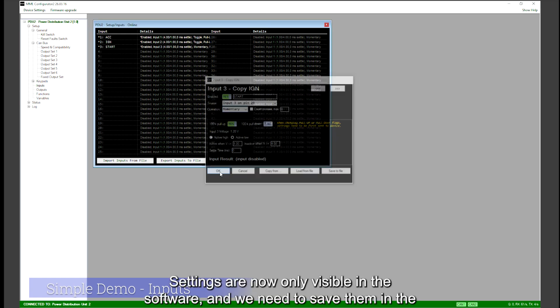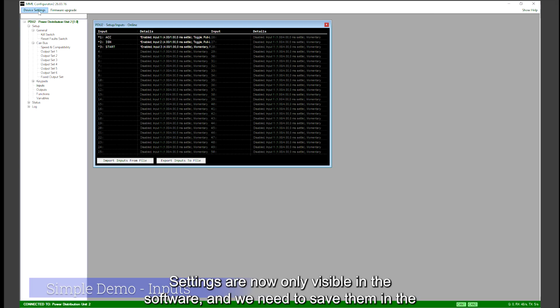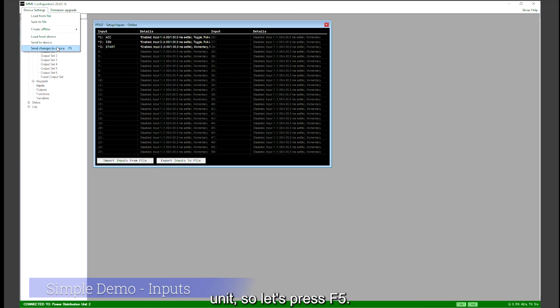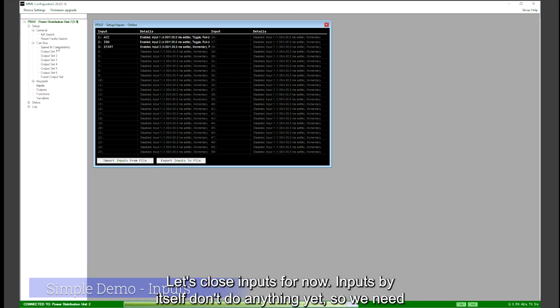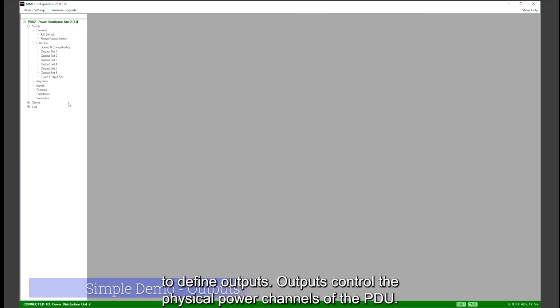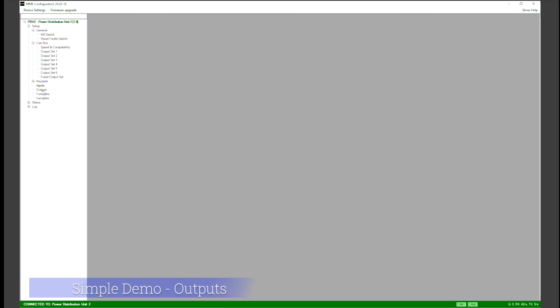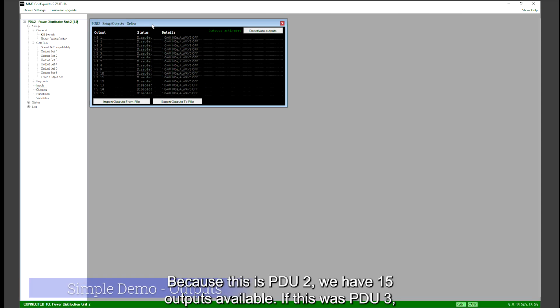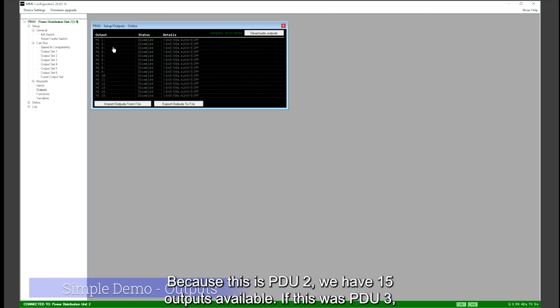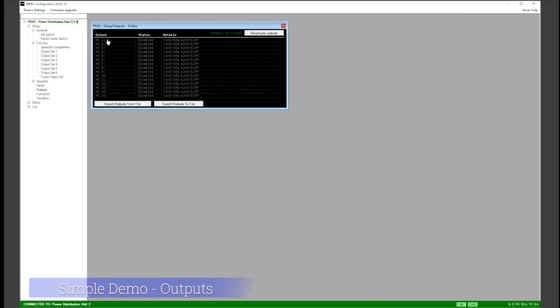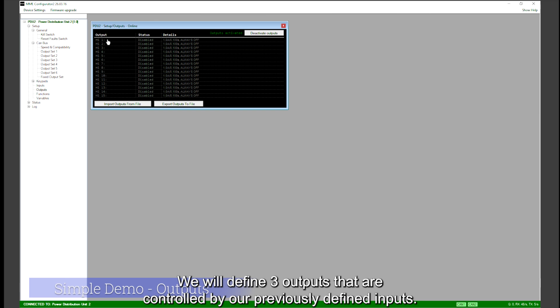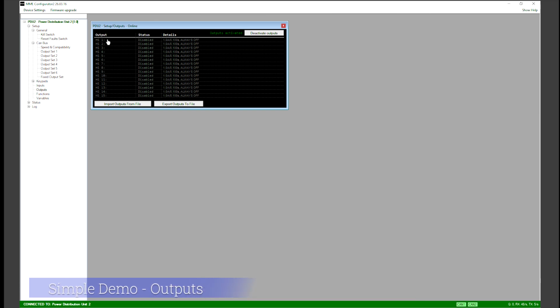Settings are now only visible in the software, and we need to save them in the unit, so let's press F5. Let's close inputs for now. Inputs by themselves don't do anything yet, so we need to define outputs. Outputs control the physical power channels of the PDU. We click Outputs. Because this is PDU 2, we have 15 outputs available. If this was PDU 3, we would have 38. We will define 3 outputs that are controlled by our previously defined inputs.